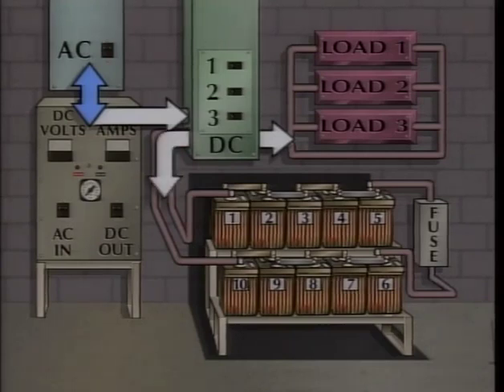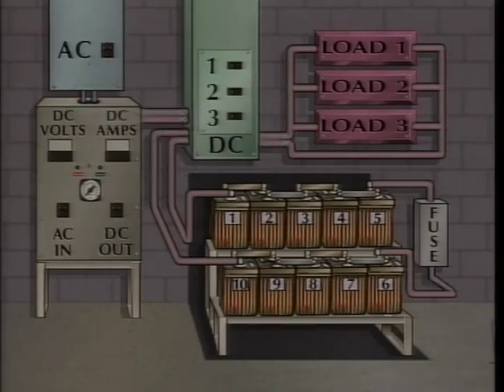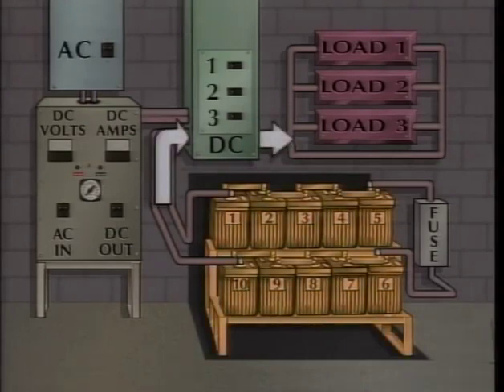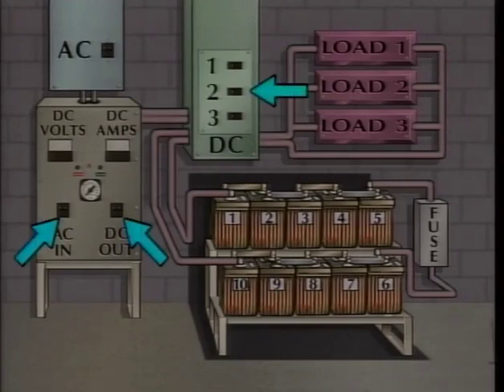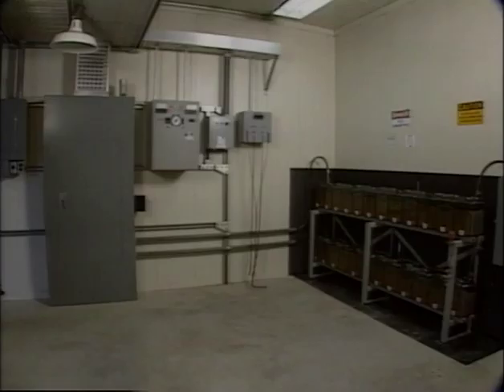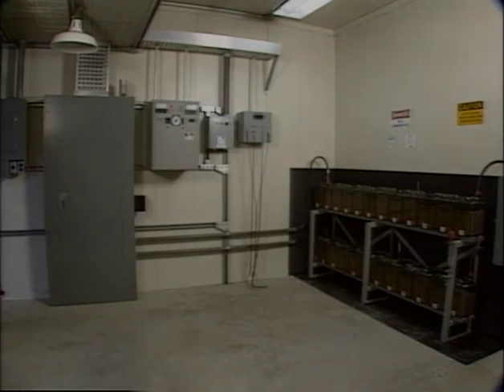If something should happen to interrupt alternating current input to the charger or direct current output from the charger, the battery would immediately supply all of the direct current to the DC loads. The breakers in a DC control system are operated in a specific sequence when a battery charger or a battery is replaced. Because DC control systems can vary, it's important to become familiar with your company's DC systems and how they work.